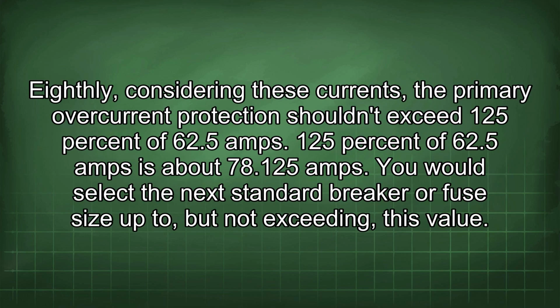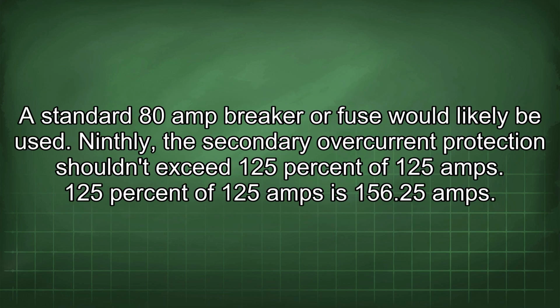Eighthly, considering these currents, the primary overcurrent protection shouldn't exceed 125% of 62.5 amps. 125% of 62.5 amps is about 78.125 amps. You would select the next standard breaker or fuse size up to, but not exceeding, this value. A standard 80 amp breaker or fuse would likely be used.